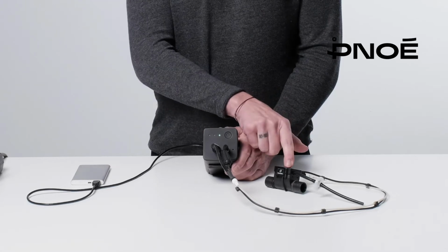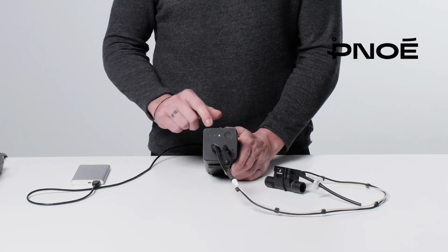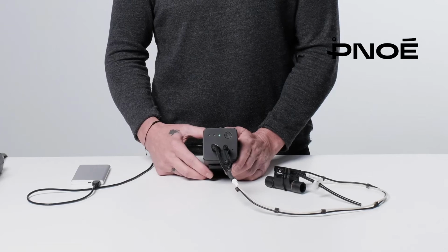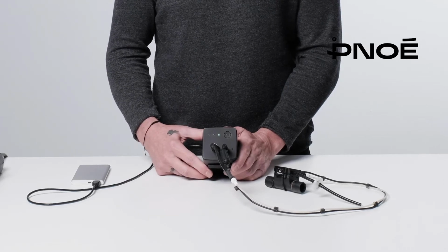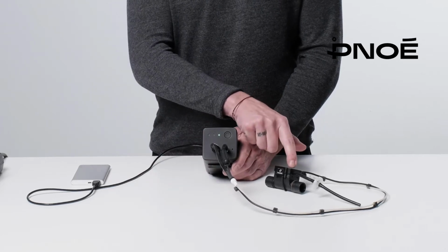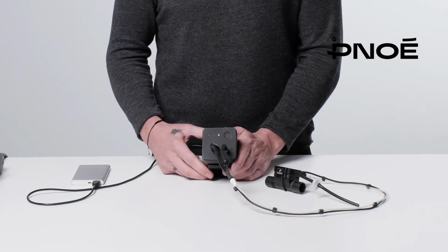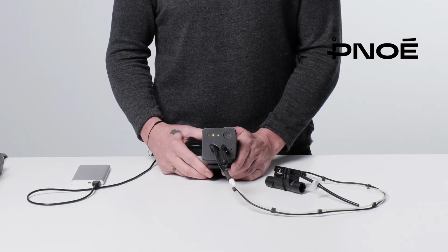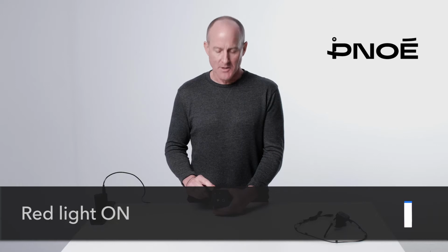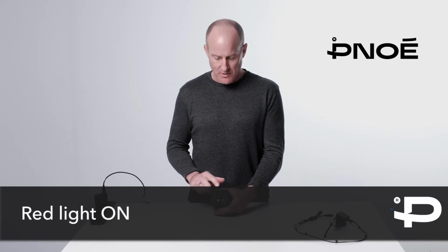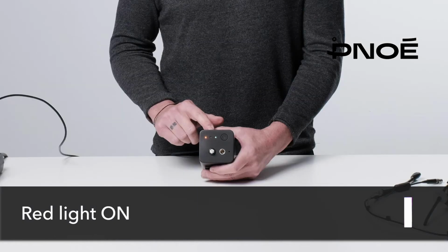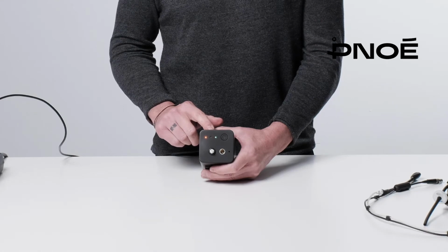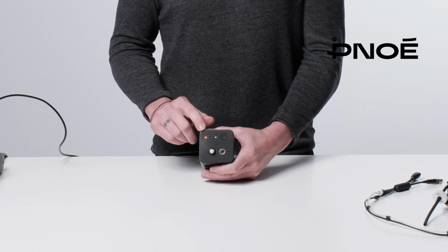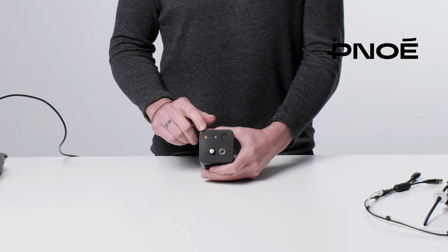It's imperative that the flow sensor is attached to the device for a minimum of 10 to 15 minutes before testing in order to allow the unit to warm up appropriately. So therefore, plan your testing accordingly. A solid red light on the PNOE device indicates that the internal battery power within the device is too low and it must be charged. If there's a solid red light, you can no longer calibrate nor complete a test.